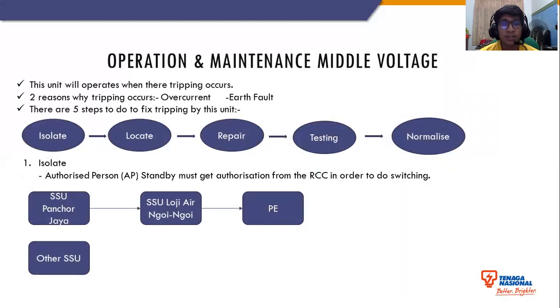For isolate, the authorized person standby must get authorization from RCC in order to do the switching. In this situation, the AP standby will isolate the incoming SSU where the problem is, at the incoming outgoing SSU Panchor Jaya and the incoming SSU Loji Air Ngoi-Ngoi. So this one has tripped. Therefore, we isolate it. Then we use the NOP from the other SSU. We put in the other SSU and we give current supply to the SSU Loji Air Ngoi-Ngoi. Then the current is back to normal while we can fix the broken one.